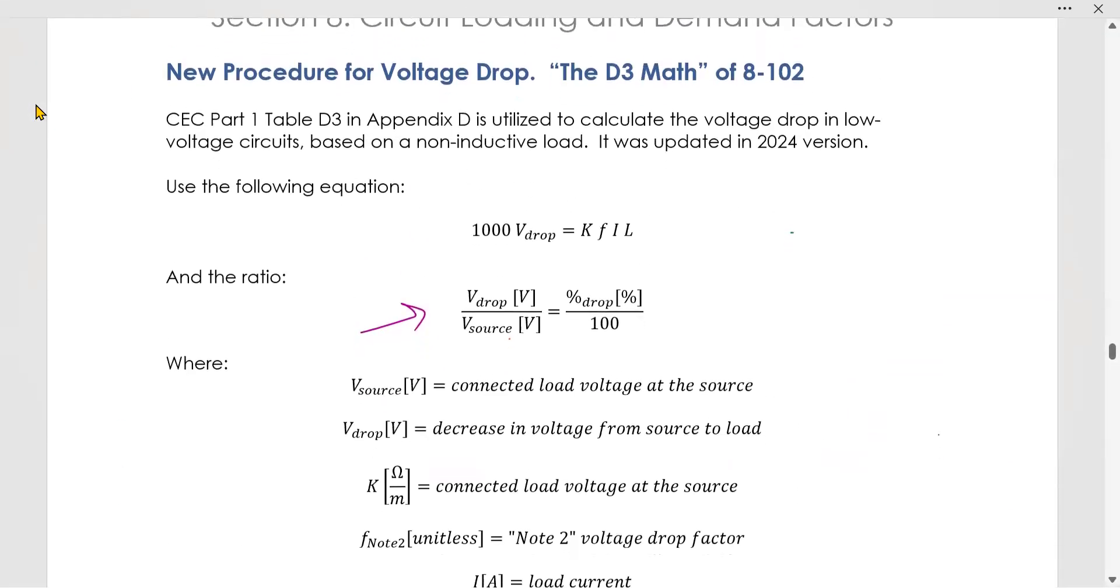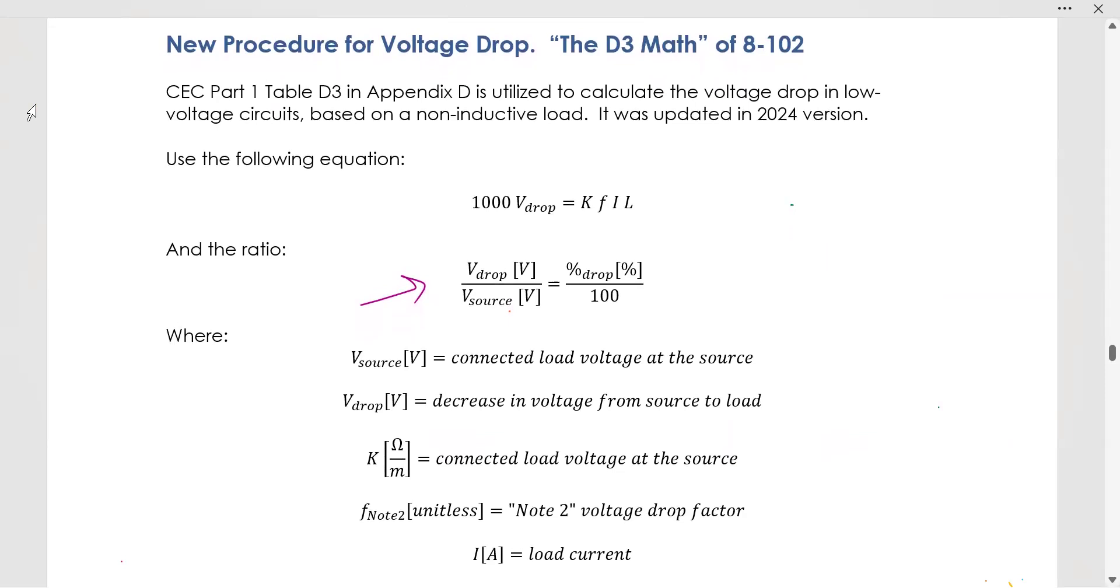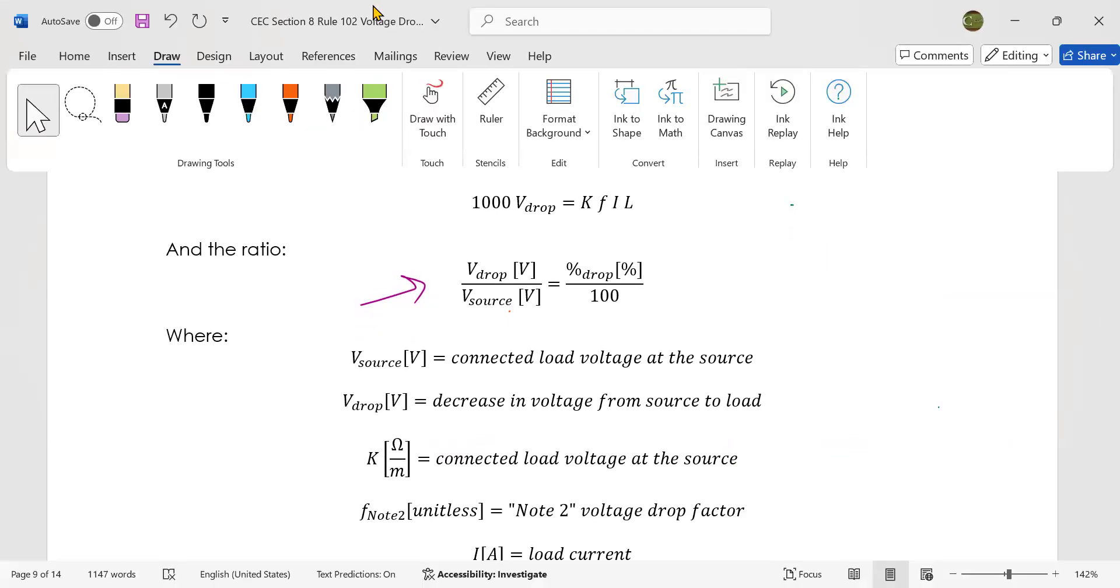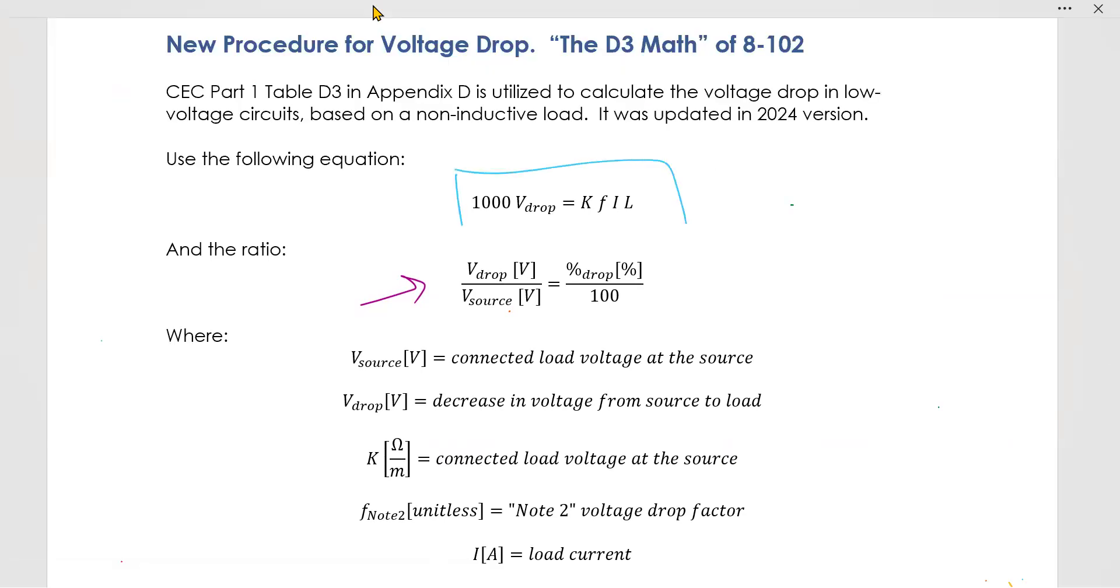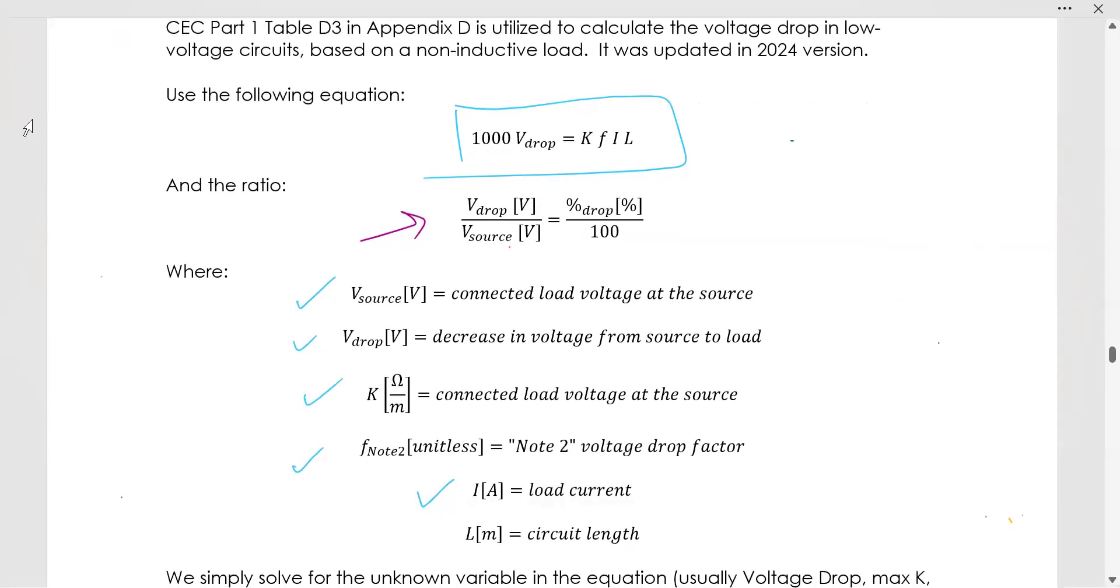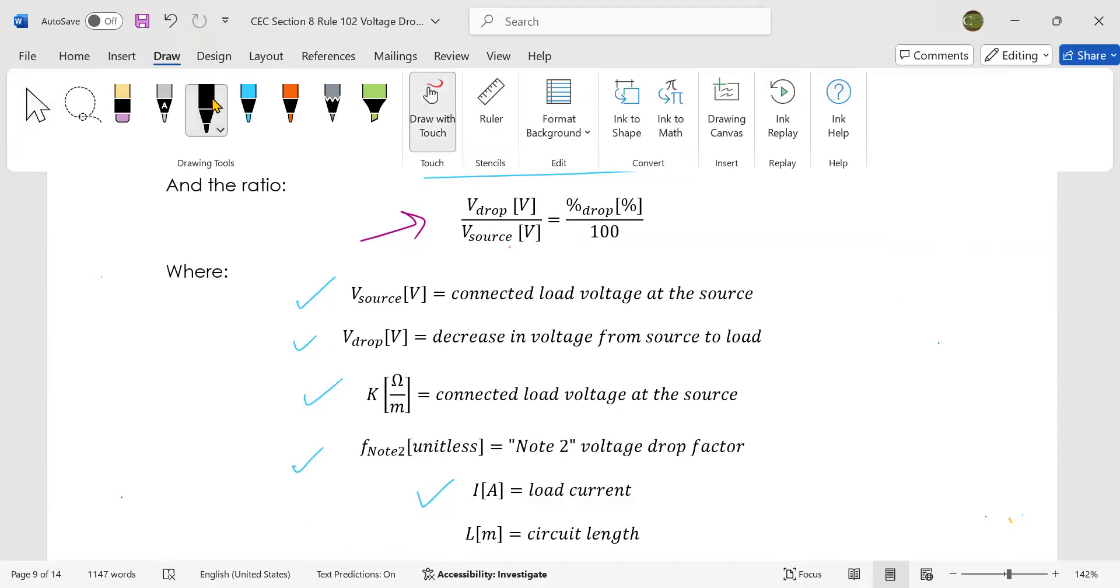What I have said so far is the new procedure for doing the voltage drop calculations in the 2024 electrical code simply means that you have a formula and you have to sub in the voltage source, the voltage drop, K value, and a factor that is called a factor from note 2, and then the load current and the length. You solve for whichever variable you don't know.